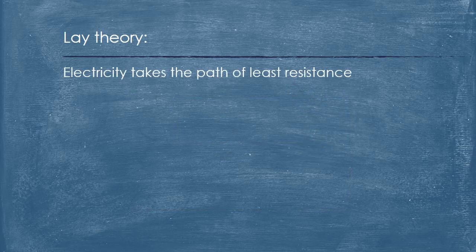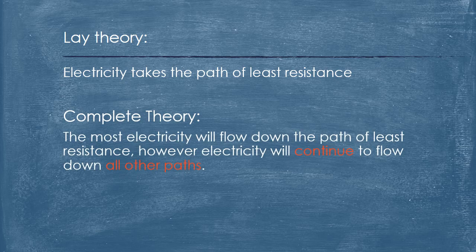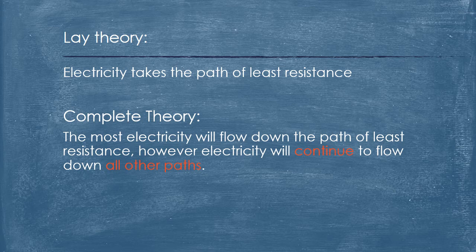So going back to our lay theory, that electricity takes the path of least resistance. Well, demonstrably, that is not correct. So here is the proposed more complete theory, and that is the most electricity will flow down the path of least resistance. The most electricity will flow down that tree, flow into that fault, set it on fire. However, electricity will continue to flow down all other paths available to it.